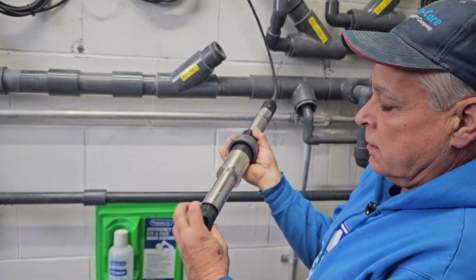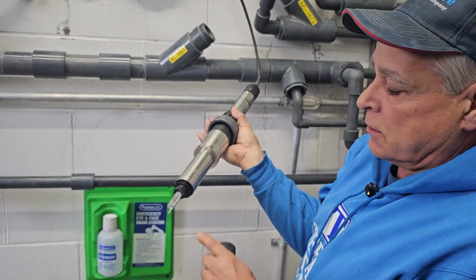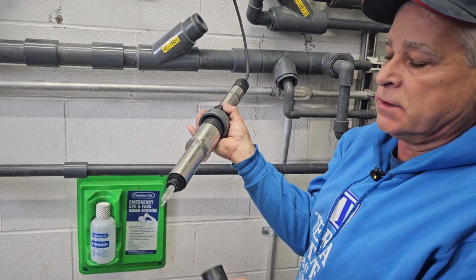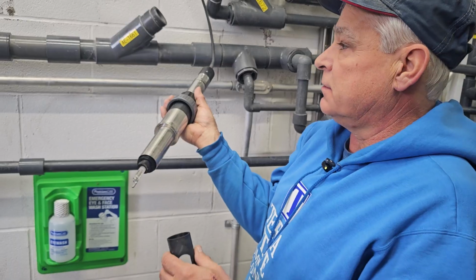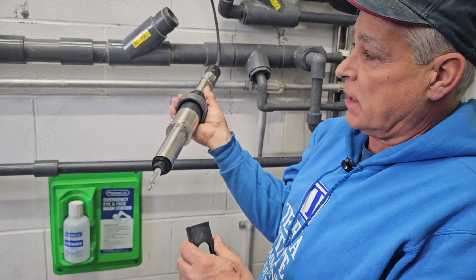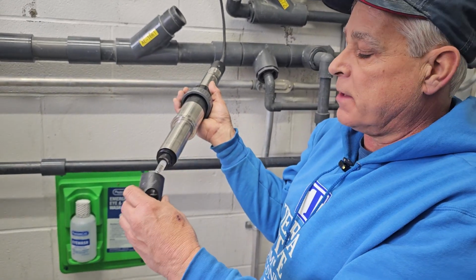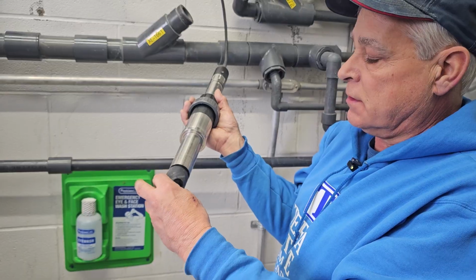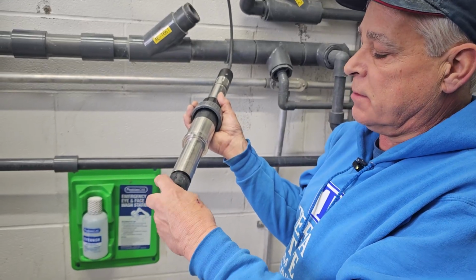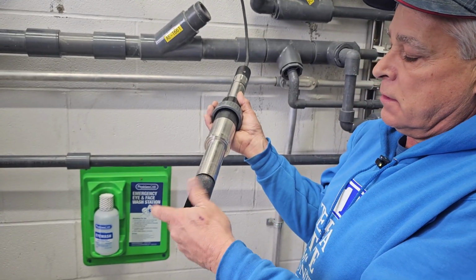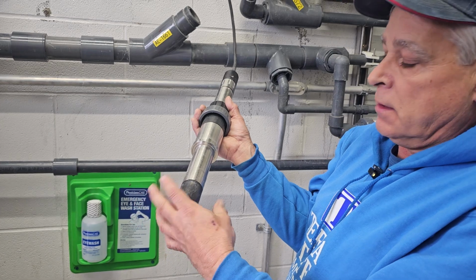Unscrew the protector, and I'd recommend, like we did this morning, wiping these. Now these sensors, if the process piping is not going to remain wet, we're going to have to store them wet. pH probes need to be wetted all the time.